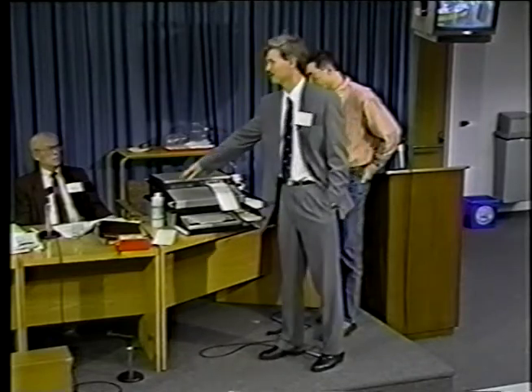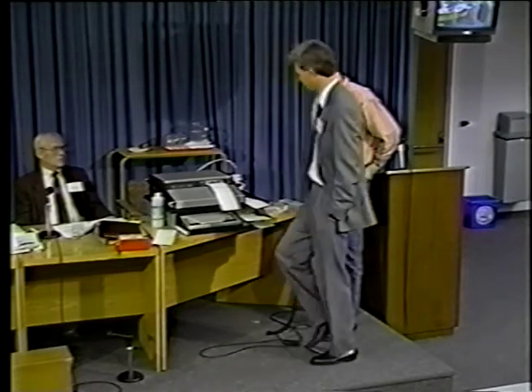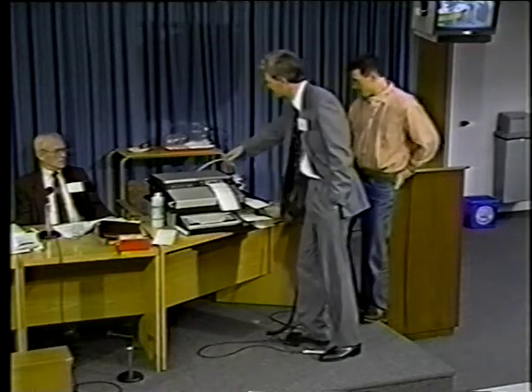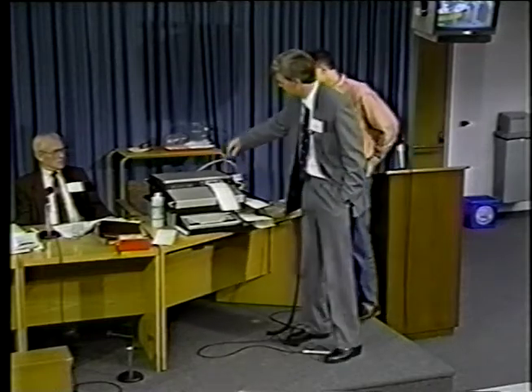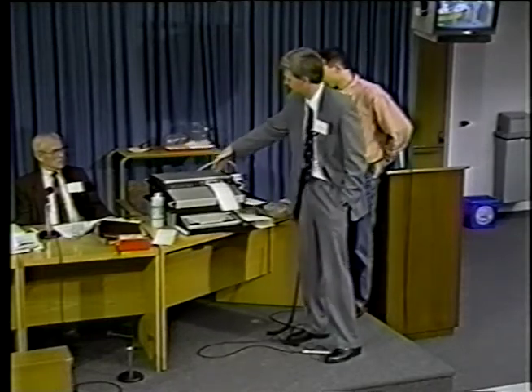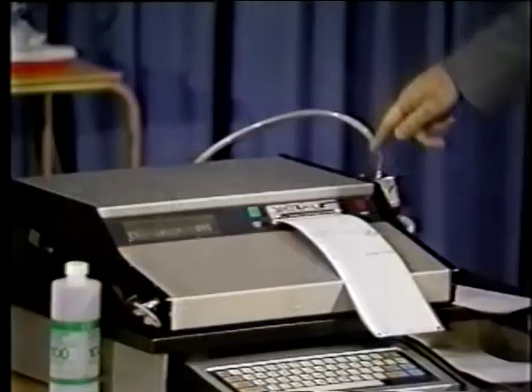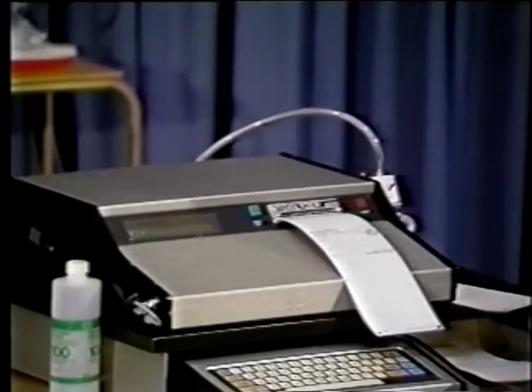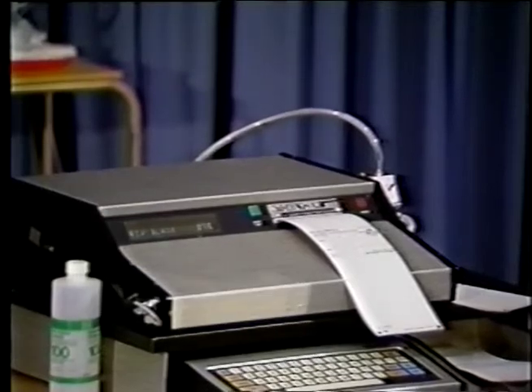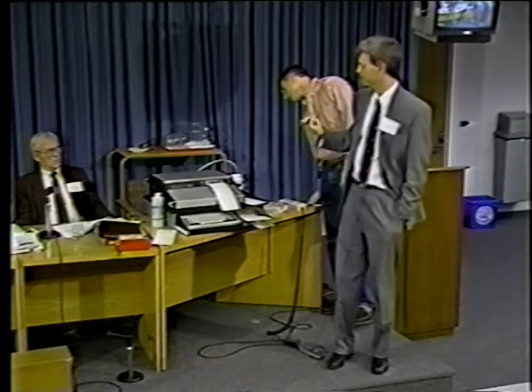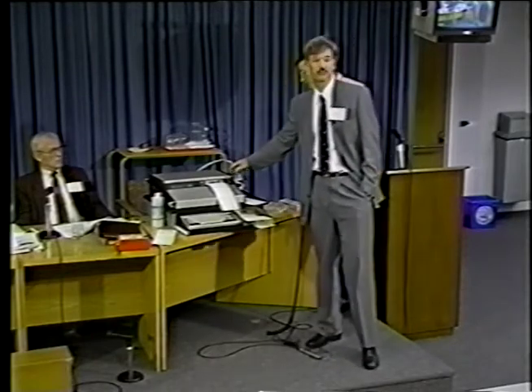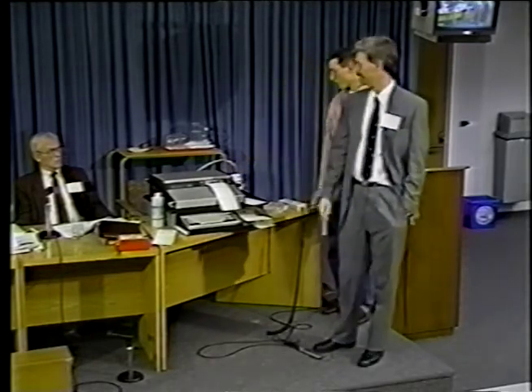Okay, what it does then is do a flush, and it does 10 internal checks. There's 10 arrows that go across. It's checking the microprocessor, stability of signal, drift, things like that. And then we're doing a calibration check. The pump is activating, and the air is recirculated through the sample chamber from the simulator. The thing with the simulator is we will always get a result of 100. That's the target value. There'll be no table of values, no room temperature, nothing like that. It will always be 100. And in this case, I think the result was 95. So the instrument is reading about 5 milligrams low.